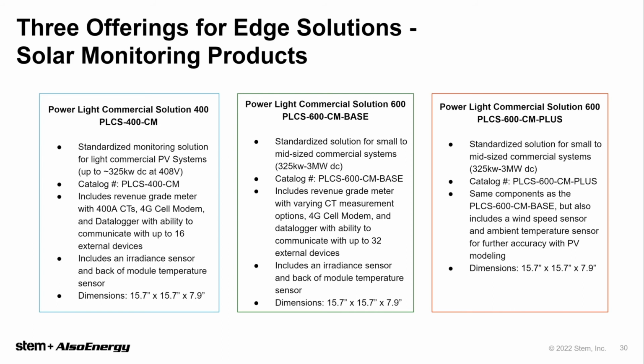So as you can see here, it says up to 325 kilowatt, but the real limitation is actually based on the max amps of the system, because the PLCS 400 always comes standard with 400 amp CTs. Inside of the device, we also have a revenue grade meter, of course, to connect to those CTs and provide accurate production data on your system.